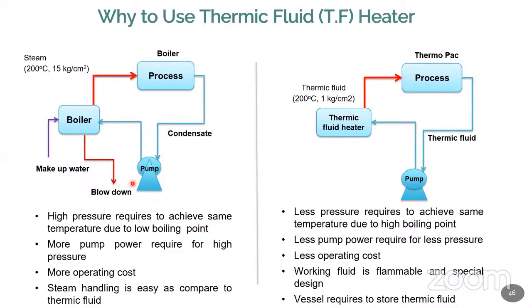But the only advantage is that steam handling is very easy, because the temperature is lower. And also the pressure, of course, we have valve control always available, but the steam handling is somewhat easier compared to the heated oil. You can see that when steam blows out in the system, it is also harmful, but compared to the heated oil, it is not that harmful. Of course, the oil has a higher harmful effect.